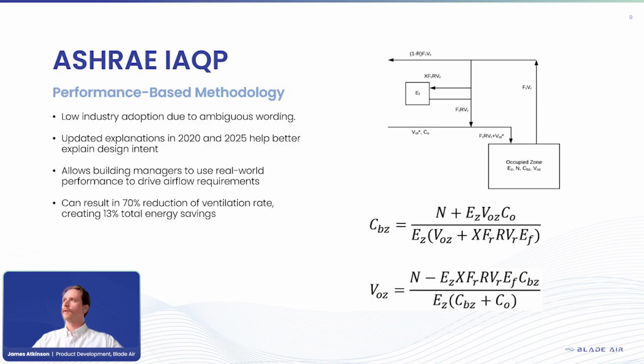It places a more stringent emphasis on validation after the fact instead of a prescriptive standard that just says, dump in a bunch of fresh air, hope for the best. Up to 13% of total energy savings. That's because of the reduction in treatment energy, but with our technology, you can also save on fan energy.